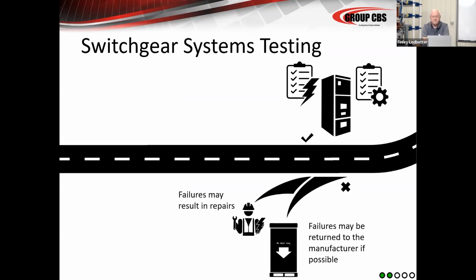Basically, you find a lot of failures. You find a lot of issues at this particular point. When the switchgear comes together with the breakers, you open and close, test the interlocks, look at the rejection mechanisms, look at the MOCs, the TOCs, the controls, check that all the CT jumpers are correct, all the bus joints are correct. There is a lot of diligence that needs to be conducted, because if you do a good job in acceptance testing, obviously the chance of your switchgear living a long and fruitful life is much greater.